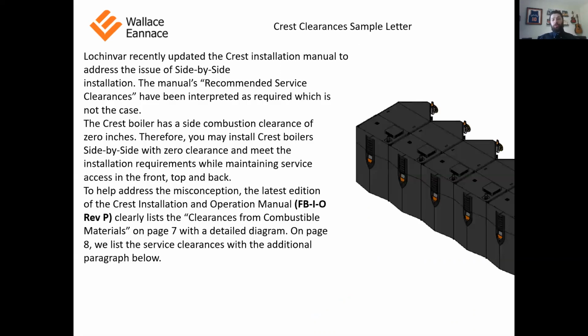When you talk about the Crest, this is a letter we can send out. Basically, what we're showing, you can put these things side by side. That's right, side by side, no clearance. All your connections are in the back, and your video touchscreen is in the front. So in summation, zero side clearance is required on the Crest. Now, it's a large boiler. In the condensing class, it is about average to large size. So side by side really closes that gap. It takes up about the same amount of space in an average installation, which, you know, in New York City, that matters.